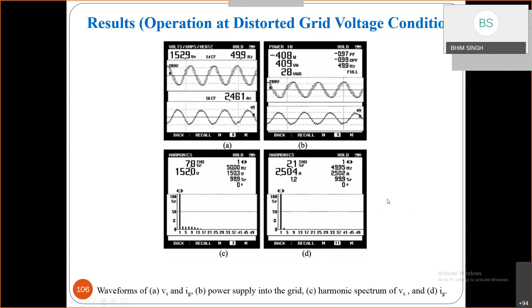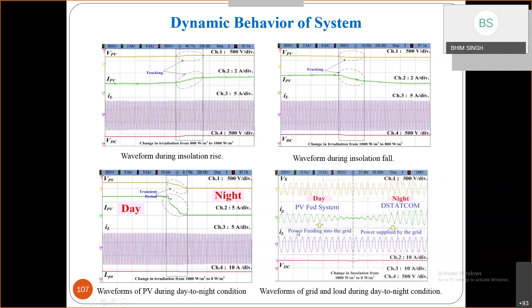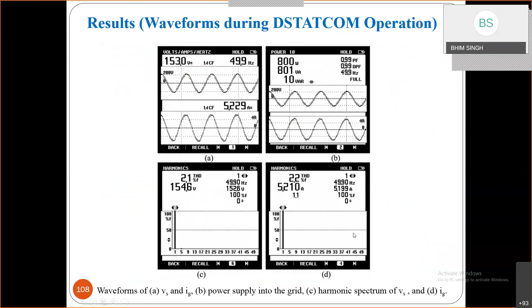It works whether solar generation is increasing or decreasing. Typically in the daytime, it compensates by putting power to the grid and also compensating the load. At night, it compensates the load, but power comes from the grid, so the grid current phase changes automatically: at night it takes power from the grid, during the day it puts power to the grid after feeding the load. We were able to test all this properly, and the algorithm reduced the current THD to 2.2%, with voltage THD around 2.1%.